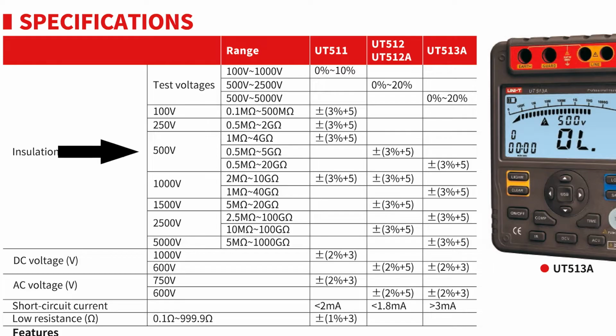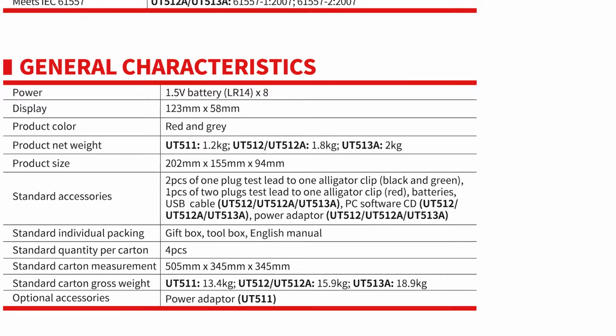Using 100 volt, you can measure resistances from 100 kilo ohm to 500 meg ohm. As the two other models don't have this low voltage, it's not possible to measure values below 1 meg ohm. Otherwise, the UT-511 can measure values only up to 10 gigaohm, while the others can measure up to 100 gigaohm. All models have different weights and different accessories.